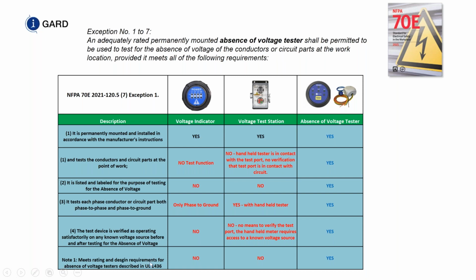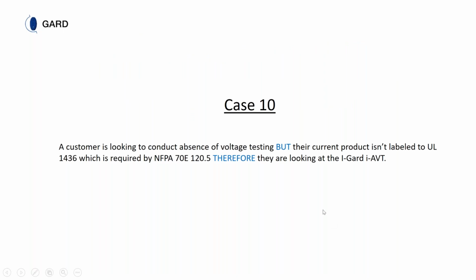Meets the rating and design requirement for absence of voltage testers described in UL 1436. The voltage indicator does not. The voltage test station does not. The I Gard IAVT does. So case number 10. Customer is looking to conduct the absence of voltage. Oh, I went the wrong way.